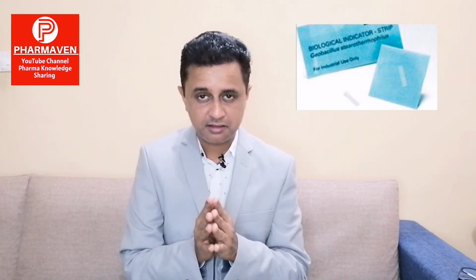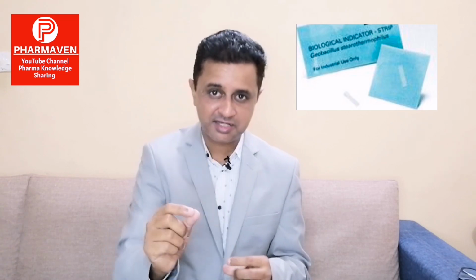For example, if we are placing the BI or sensor downwards, then condensate will go through the BI and the sensor. So we will have a temperature drop in the sensor also, and we will not get the BI killed properly. So the BI should be kept upwards. The sensor also has to be kept upwards. Then, because of condensate, it will not get temperature fluctuation or BI failure. So BI placement is very important and should be thoroughly looked at.